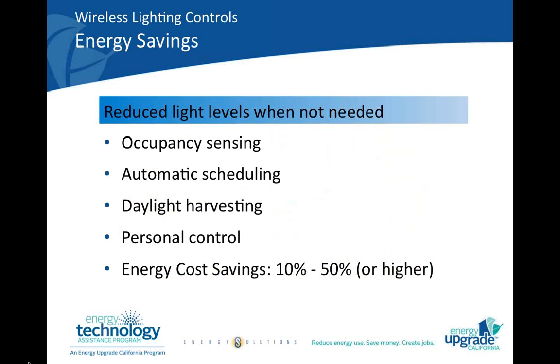So as I was mentioning on the previous slide, the savings opportunities from wireless lighting controls really come from a few different places. They can all be layered on top of each other to maximize your savings. The first is through occupancy sensing, the second being through automatic scheduling, the third being through daylight harvesting, the fourth being through personal control. So each person can control their own fixture if they would like, depending on whether you want to give them that control, simply by going online. And then lastly, all of these saving strategies can be layered on top of each other with different levels of priority. So we estimate that the cost savings from these types of projects can be anywhere from 10 to 50%, which is also really dependent on the individual space itself. Next slide, please.